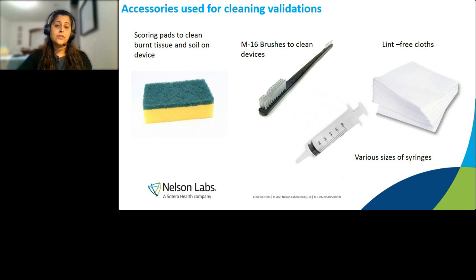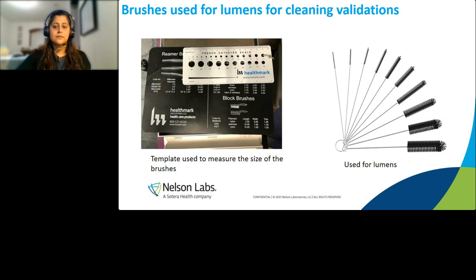Now, if the IFU does not have a supply specified and we think that we need it for the validation, like ultrasonic cleaning, which is another one that a lot of manufacturers do not specify, but if it can be cleaned manually without the ultrasonic part of it, then we would add that to it. Some of the brushes for the lumens.